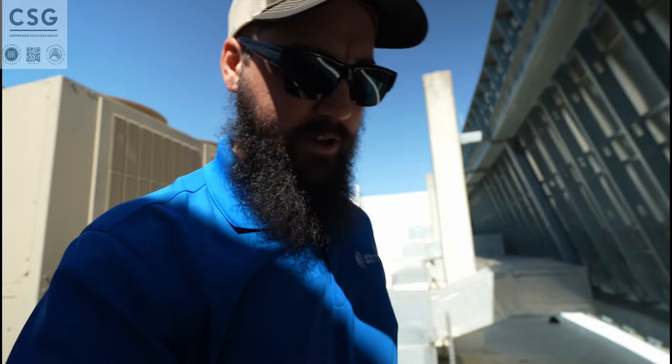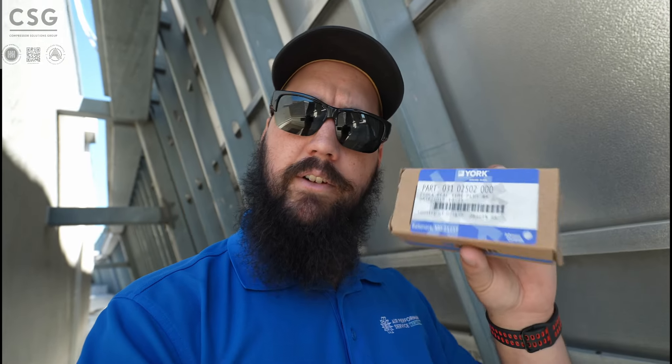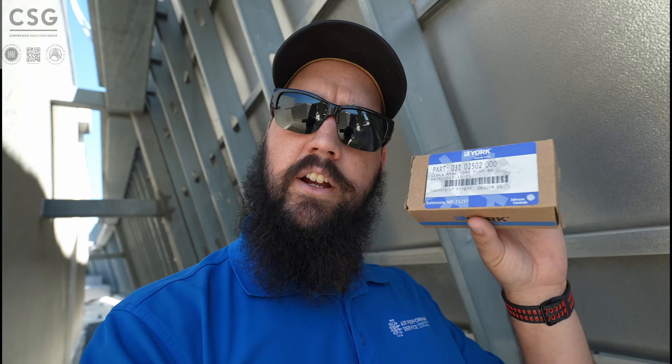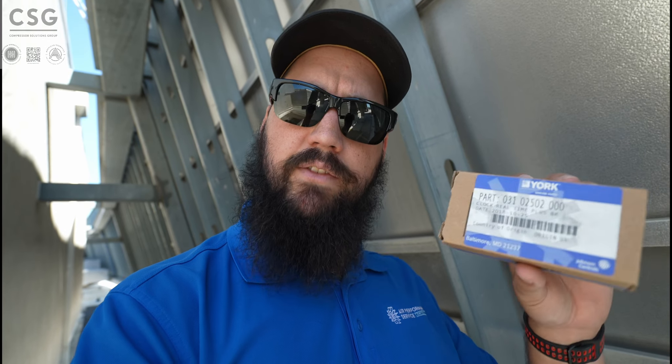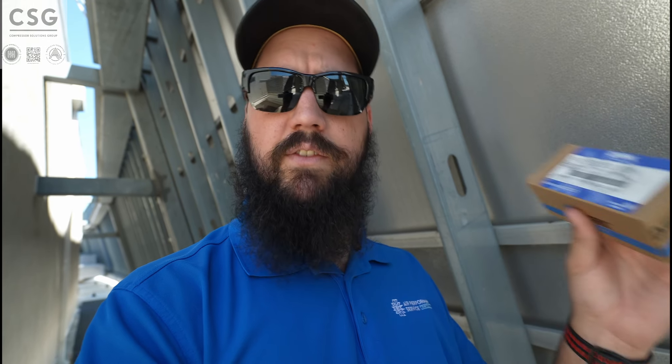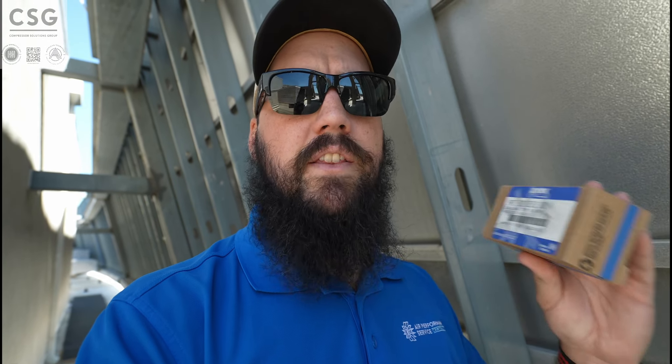So the main thing that happened here - the chiller got shut down in order to do a condenser fan change out. Those BRAMs have a battery in here that saves the data. That battery had failed. It was down for like two hours to do the fans, and in that time when the power first comes back, it shows invalid serial number or something like that. That tells you what you need.